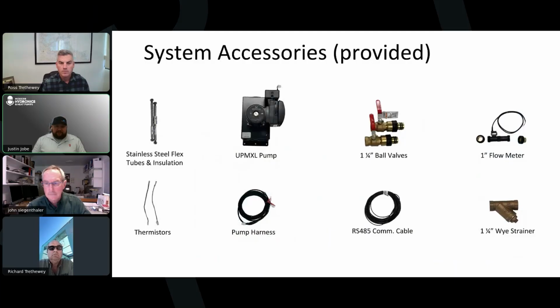These are the accessories that come along with it. We do have the same stainless steel flex tubes with insulation that comes as an install kit, for vibration isolation on the outdoor unit. We do still require our variable speed UPM XL pump, a Grundfos pump that comes in an insulated cabinet, as well as isolation double O-ring ball valves for either side of that pump. It still comes with a flow meter and a couple wiring things that come along with the install kit, and a Y strainer because the outdoor unit is using a braze plate heat exchanger.